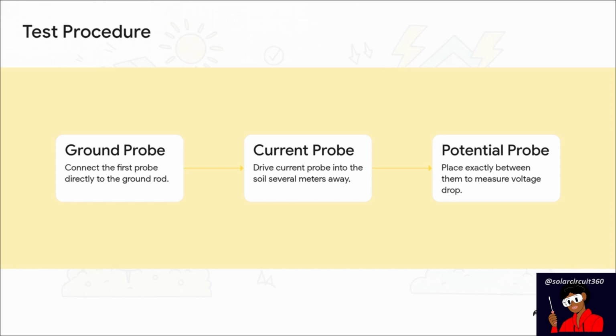Step 2, you drive a current probe deep into the soil several meters away. Step 3, you place a potential probe perfectly between the two. The tester then injects a known electrical current into the earth, measures the resulting voltage drop right in the middle, and calculates the exact resistance for you.